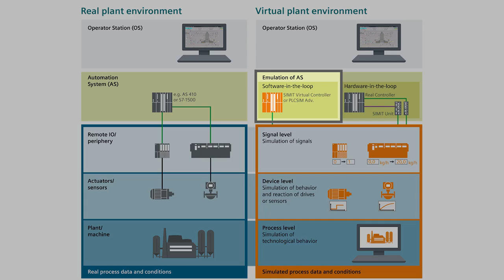In the hardware-in-the-loop configuration, the automation program is loaded via the SIMIT unit into the real automation system. The SIMIT unit is mainly responsible for emulating the bus and device level, which are not available in reality. With the software-in-the-loop configuration, nearly everything will be emulated from the controller up to the process level. Imagine that you should have all the devices of your plant available for testing—what a procurement and logistics effort that would be. Unthinkable in times of digitalization.